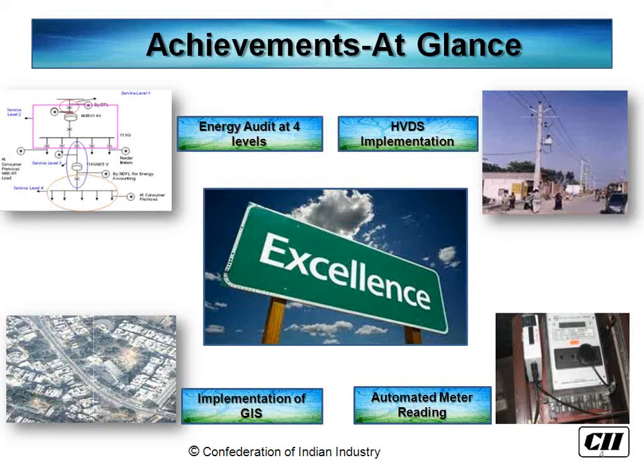And reduce our AT&C losses. We also introduced the High Voltage Distribution System, HVDS. Basically, it replaces a very large distribution transformer with smaller ones mounted on single poles, as shown in the photograph. The overhead line is an HT line, high tension line, very close to the customer. It feeds only a selected, very small number of customers. The whole idea is to reduce technical losses and reduce pilferage of power.